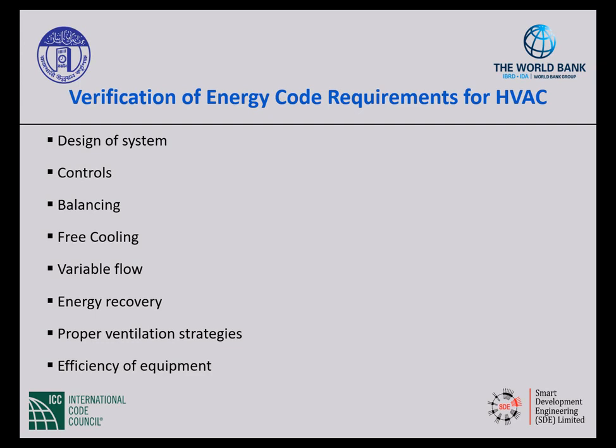use of the building is coming from. And can we shut things down when we don't need them as much? Make sure you have that system balancing. That's really pretty simple because it just tells you that it requires a written balance report provided to the owner. And then that balance report has to include how they did their air system balancing or their hydronic system balancing, etc. So making sure that you're going back there and getting that report.